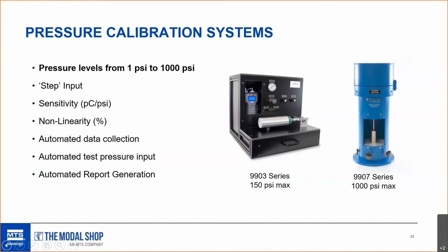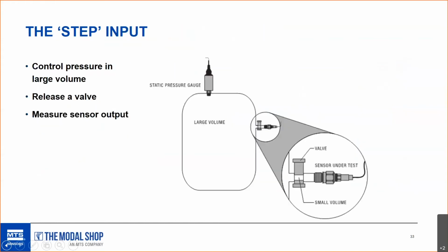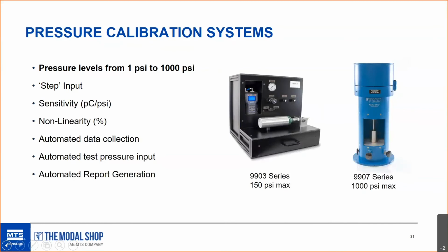And they measure using what we call a step input that I described earlier, and it calculates sensitivity. The software enables calculation of sensitivity and nonlinearity in an automated fashion. So this is the technique we talked about, the large volume. For example, I'm going to jump back a slide. The large volume in the case of the 903 is encased in a pressure vessel in the back of it. It's not visible here. And the large volume in the case of the 907 is the mid frame, about 2/3 of the way up. I'll get my laser pointer out here. It is in this area. And you'll see how small of a volume we expand that into later. And you'll see it on the 903 too.